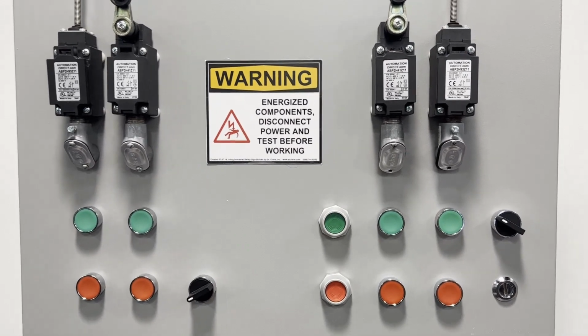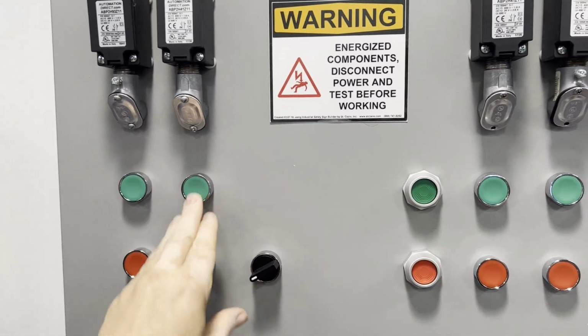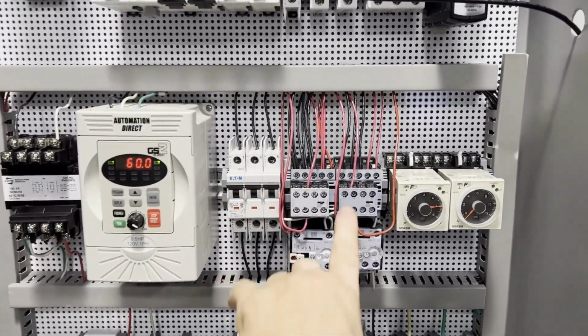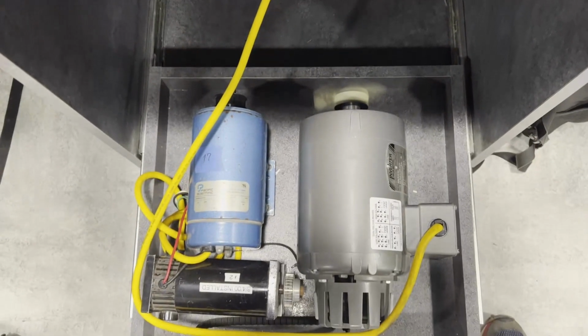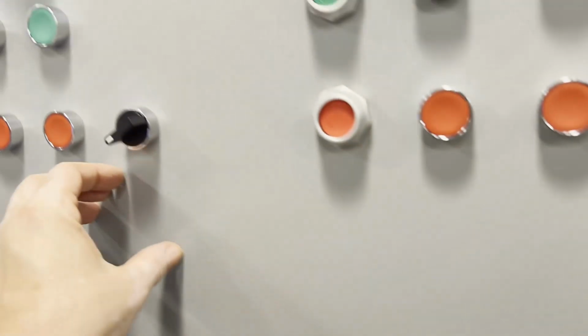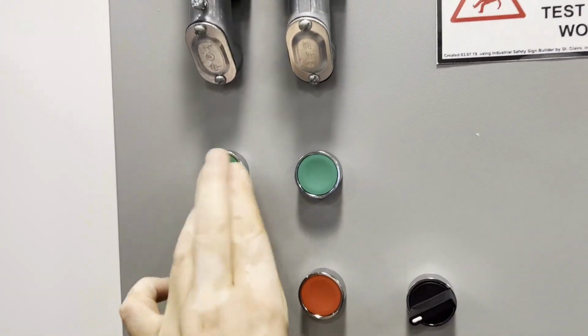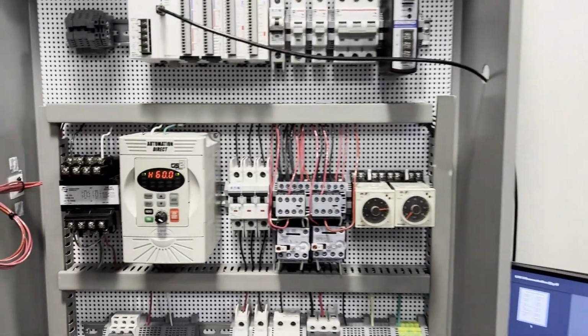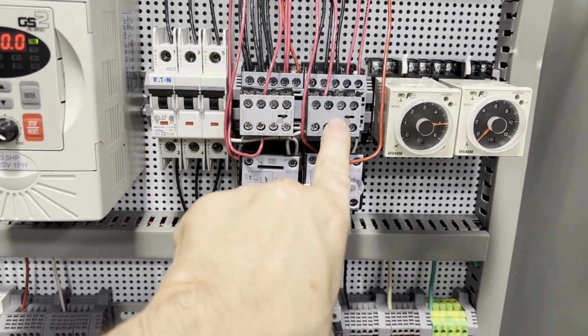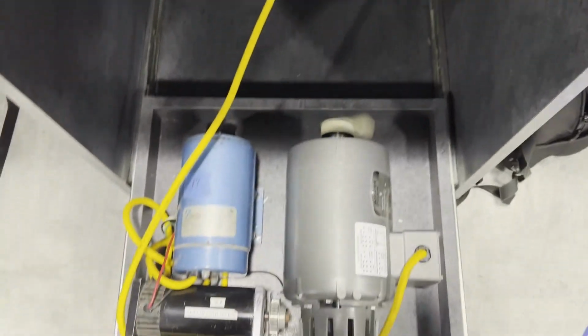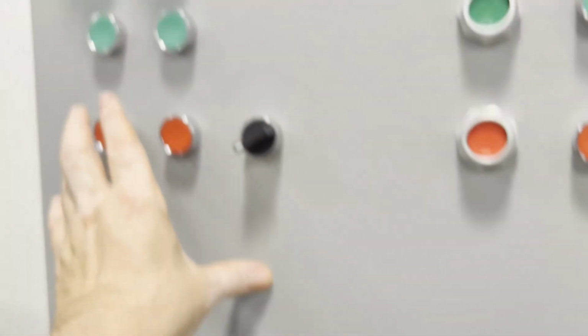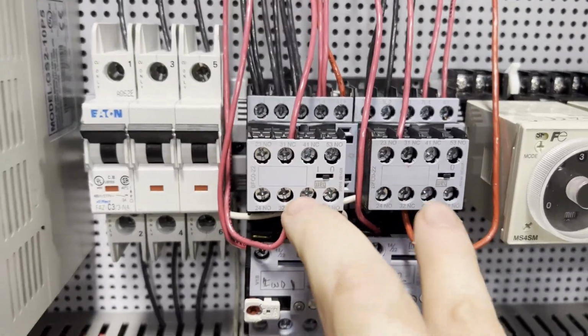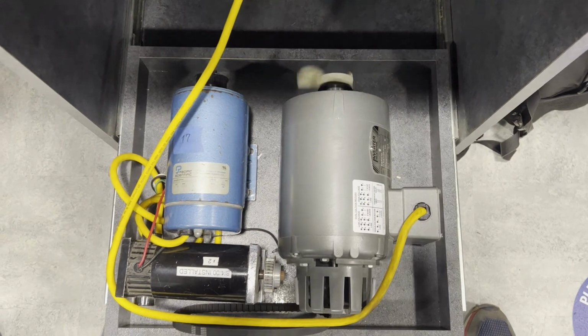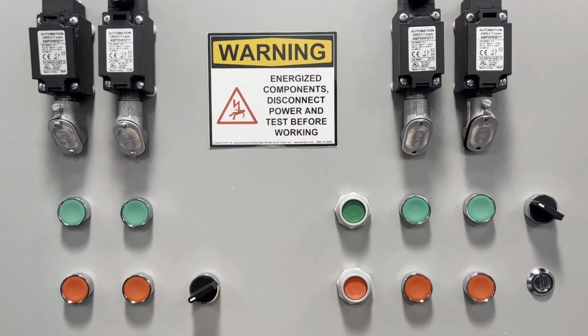Test number 8, reverse interlocks. Start the reverse. Verify reverse contactor closed. Motor turning in reverse direction. Push the forward button. Did not hear any changes in the sounds. Forward contactor still open, reverse contactor is still closed, and the motor is still turning in reverse direction. Stop. Contactor is open, and motor coasting down to a stop in reverse direction. This concludes the reverse interlocks test.